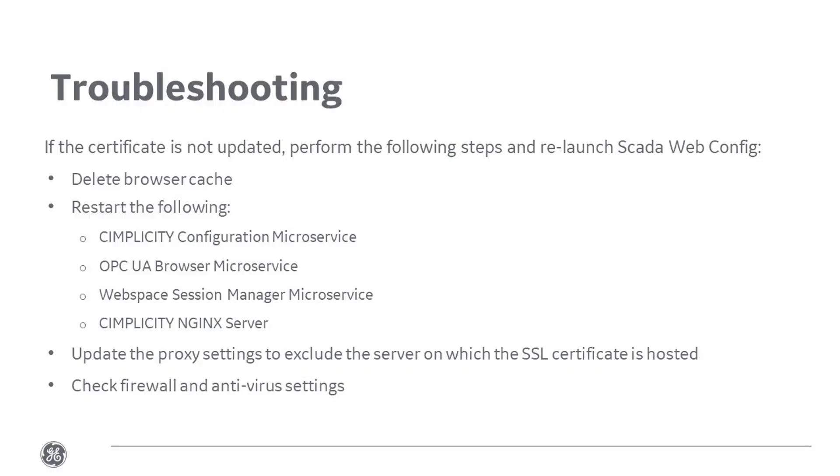If the certificate is not updated, perform the following steps and relaunch SCADA Web Config. Delete browser cache, restart CIMPLICITY Configuration Service, OPC UA Browser Service, Webspace Session Manager Service, and nginx server. Update the proxy settings to exclude the server on which the SSL certificate is hosted. Check the firewall and antivirus settings.